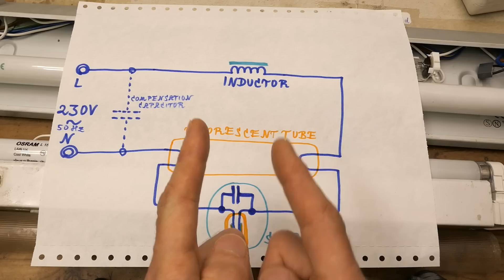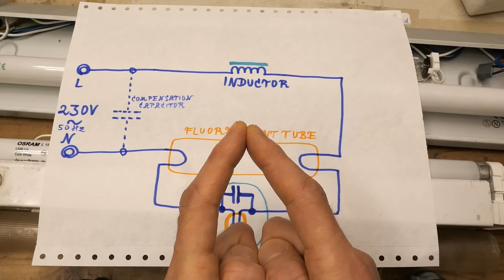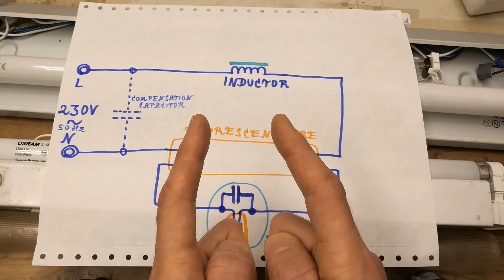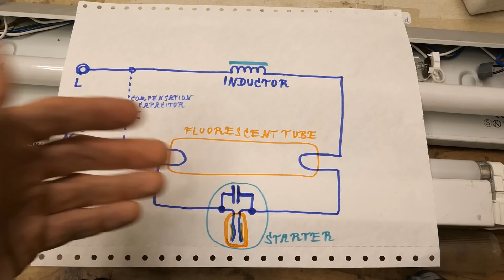But because there is the capacitor in parallel which is charged, it basically discharges when the electrodes touch and they slightly weld, and as they cool down and try to separate, it takes some time to cool enough to develop enough force to separate them. So basically the electrodes slightly welding is what creates the preheat delay.